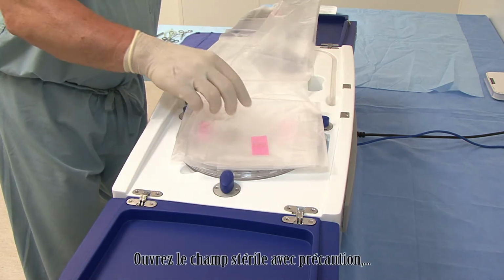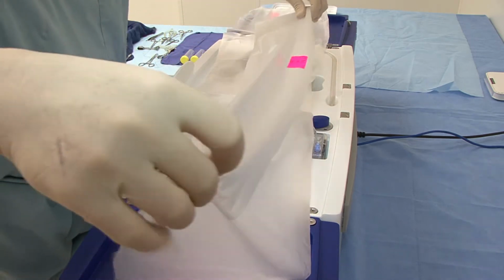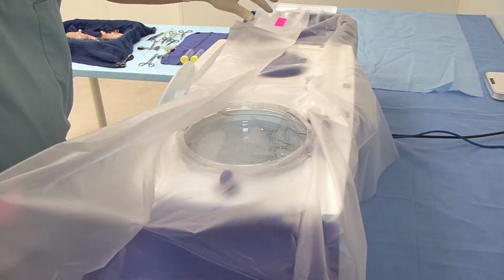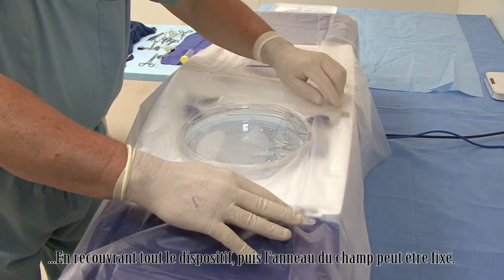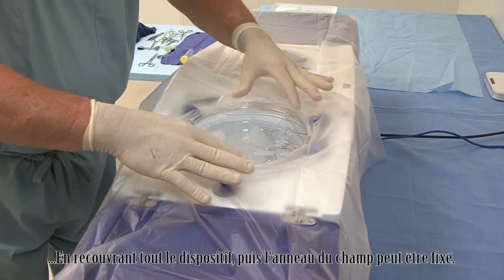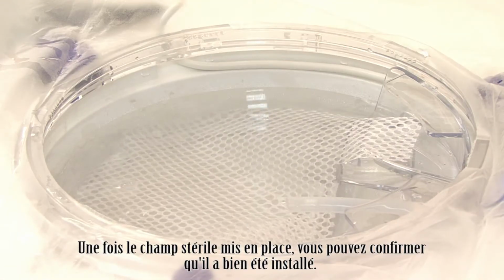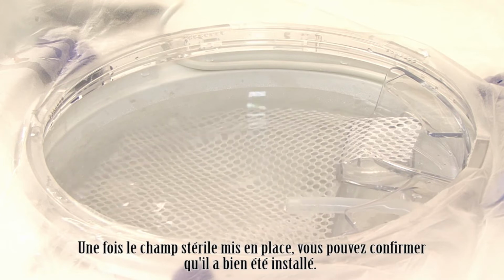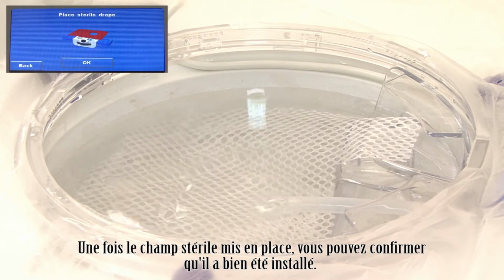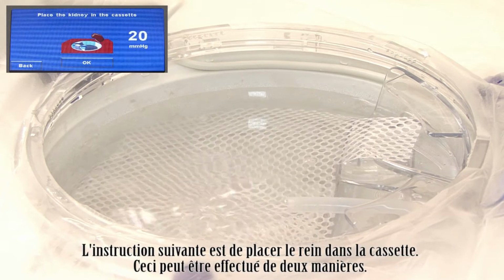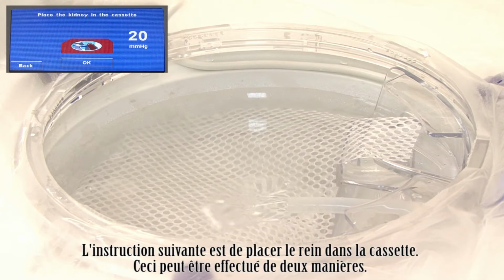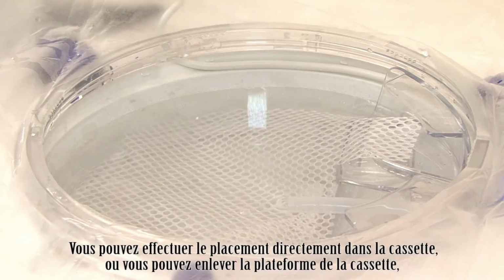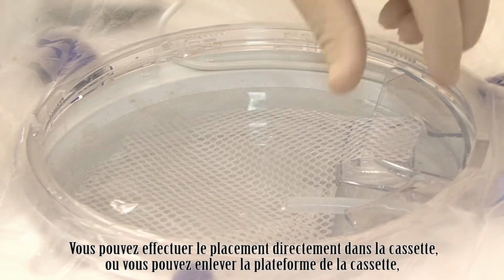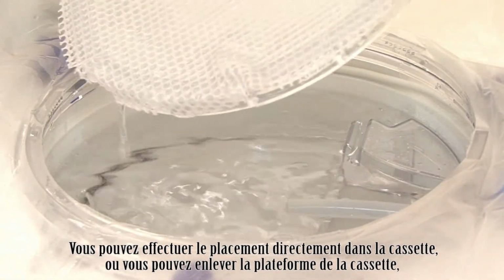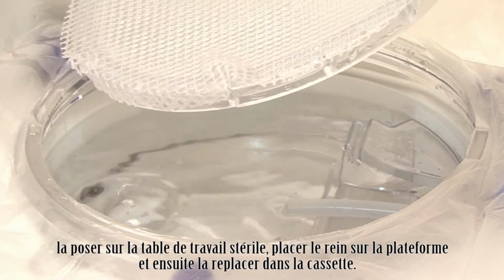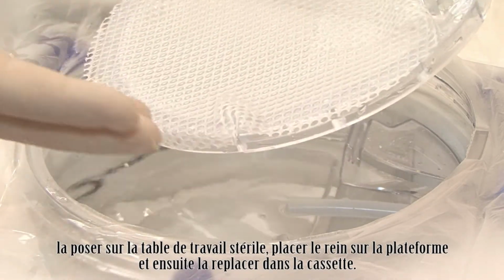Carefully open the sterile drape, covering all aspects of the device. Then the drape itself can be locked in place. After the cassette drape has been placed properly, you should confirm that the drape is in place. The next instruction is to place the kidney in the cassette. This can be performed in two ways. Either you can perform the placement directly in the cassette, or you can remove the kidney platform, take it to the back table, place the kidney on the platform, and then bring it back to the cassette.